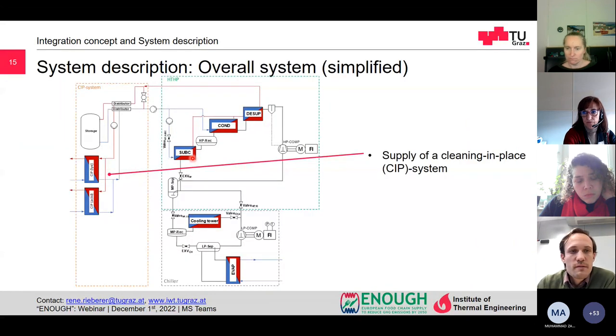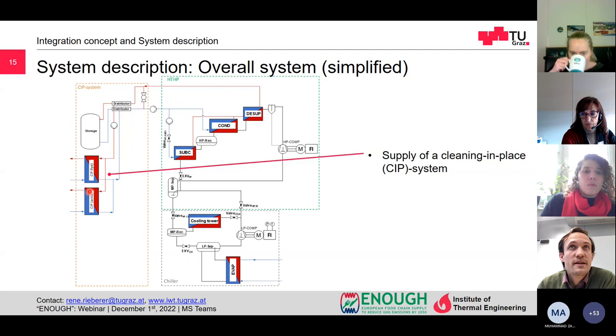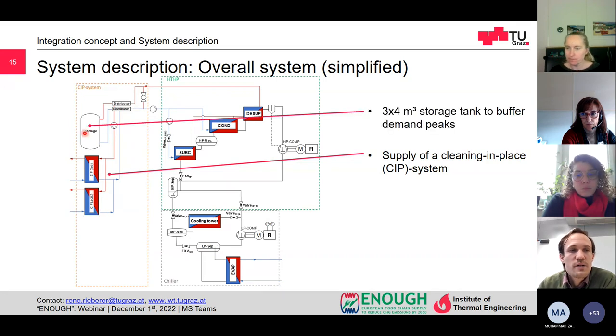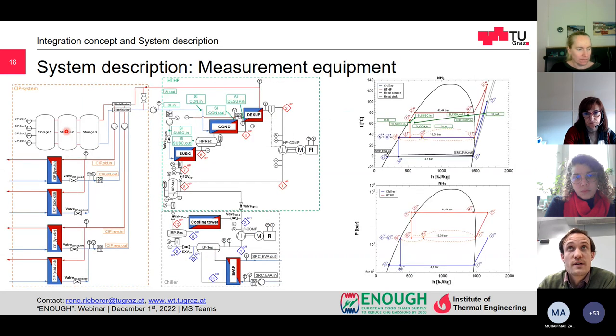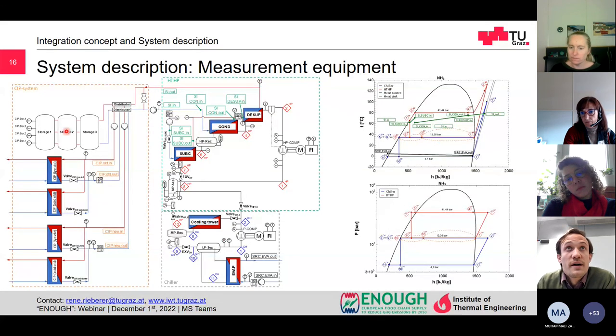The heat pump was used to supply the cleaning in place system, which consists of a lye and an acid. To buffer demand peaks, a buffer storage of around 12 cubic meters was also integrated. To have sufficient monitoring of the system, especially the high temperature heat pump was equipped with a lot of sensors. So there are pressure sensors, temperature sensors, and volume flow meters.